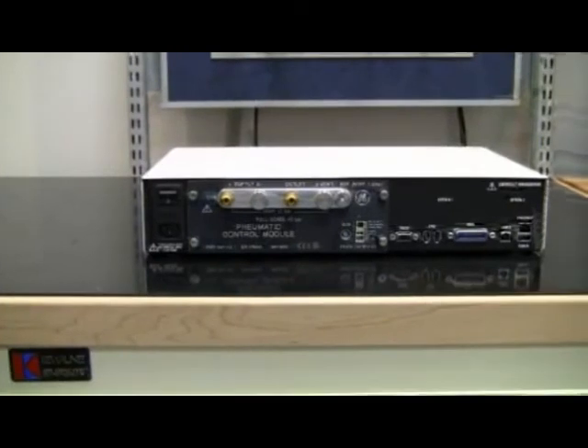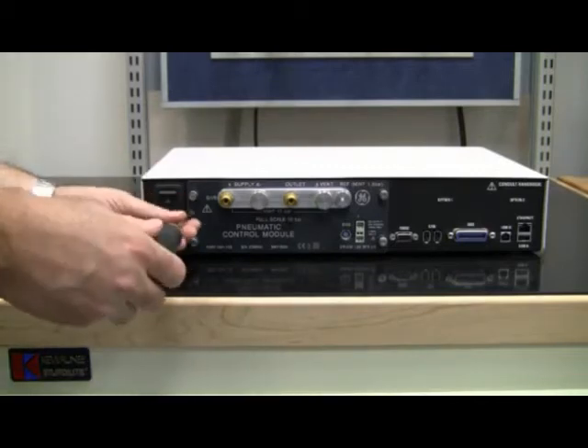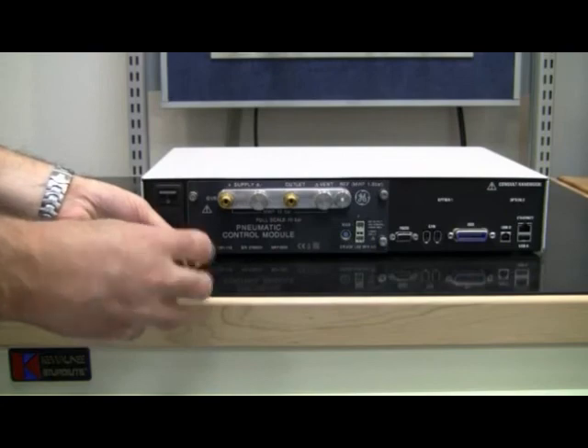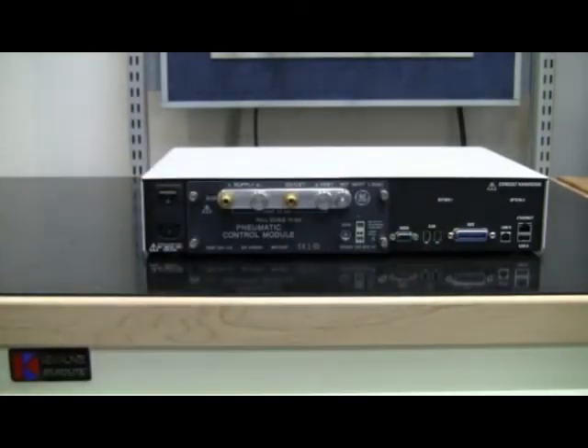As mentioned previously, PACE 5000 is designed on a highly modular platform. The control module can be easily removed to change pressure ranges or replaced with the same range when it is time for recalibration. It also simplifies the process when PACE 5000 is mounted in a rack or cabinet-based system. To remove the module, first switch the power supply switch to the off position and unplug the power cord. All pneumatic lines should be vented and disconnected. Then, unscrew the four retaining screws and slide the module out of the chassis.